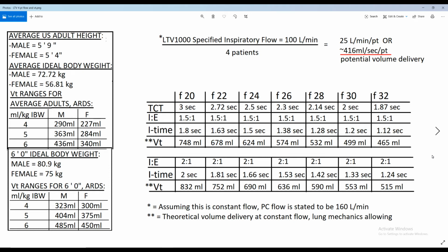The specified inspiratory flow that comes from an LTV, I went and looked it up. It says 100 liters per minute for inspiratory times between 0.3 seconds and 9.9 seconds, I believe. If we split that 100 liters per minute up across 4 patients equally, that means each one of those patients will potentially get 25 liters per minute. 25 liters per minute per patient of inspiratory flow.